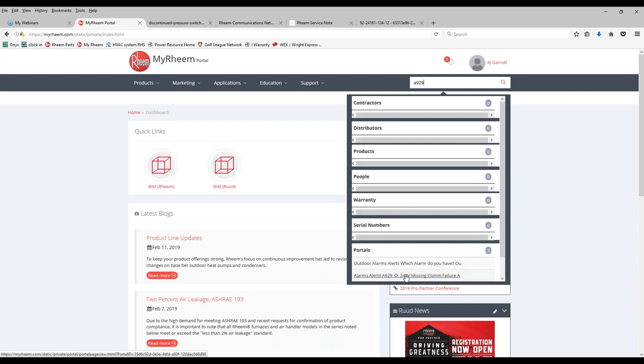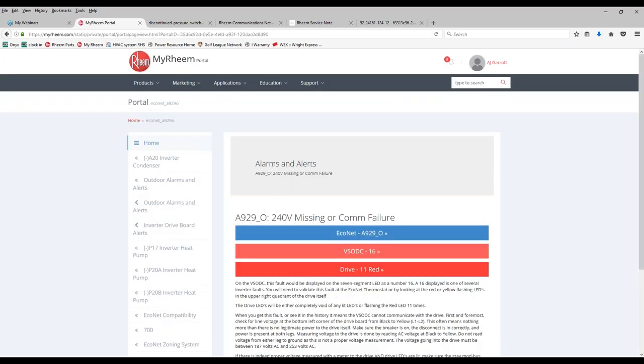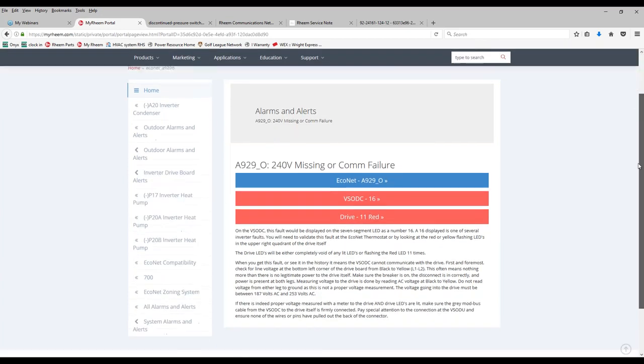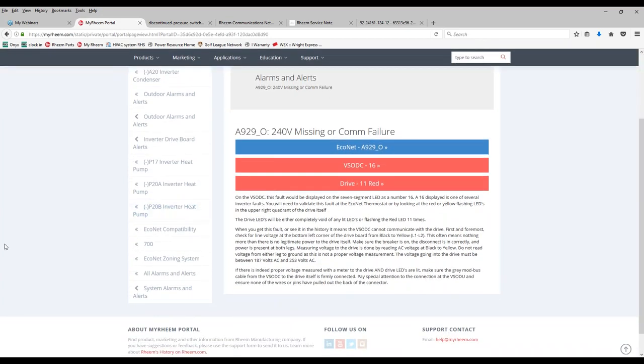You have a missing communication failure. If you click on the error code underneath that portal, it'll go to more information for that error code so that you can now see the information for the error code throughout here and how to diagnose that error code. Other things to look at, where you will see that error code at. At the variable speed outdoor unit, what it's saying here is you will get a code 16 on the outdoor unit. At the Econet thermostat, you'll have A929. On the drive, you'll have 11 LED flashes it shows. So a little bit more information there for you.